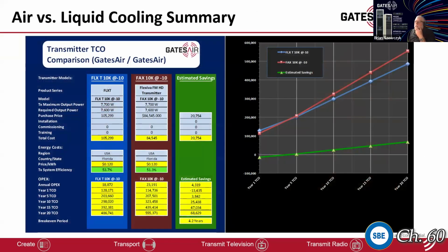And this is just a typical cost of ownership comparing a liquid cooled transmitter to an air cooled one, and you can see that the acquisition cost is going to be a little bit more. At 12 cents per kilowatt hour, with the added efficiency, the break-even point for recouping this additional amount is about 4.2 years down the road. And that's for a 10 kilowatt, which as you go higher in power, tends to be much shorter.